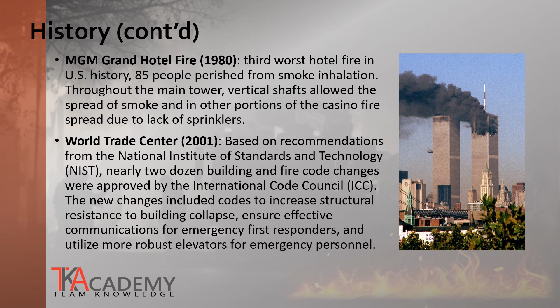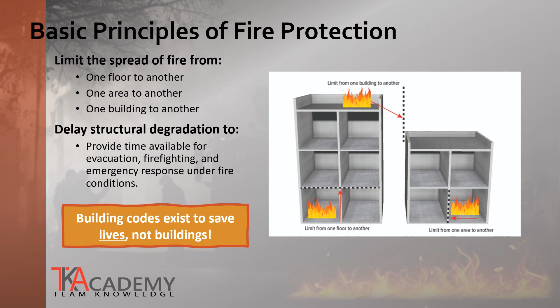There are two basic principles to fire protection. The first is to contain and limit the spread of fire from propagating to other floors, adjacent areas, and neighboring buildings. The second is to delay structural degradation to provide time for evacuation and response from emergency personnel. Fire-resistive construction and building codes exist to save lives, not buildings. A substantial portion of building codes pertain to fire resistance and delay of fire and smoke propagation.